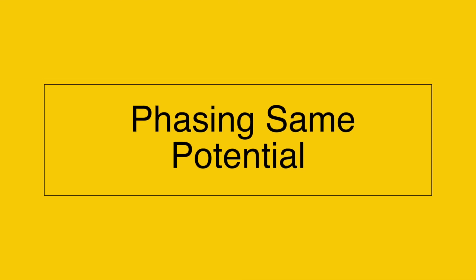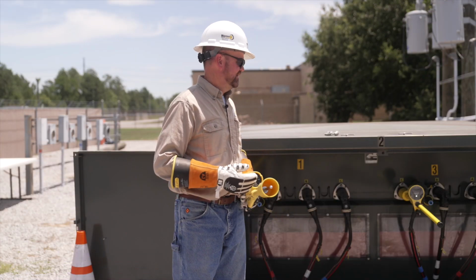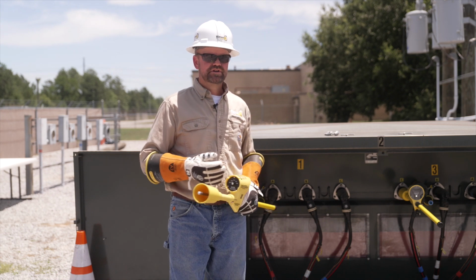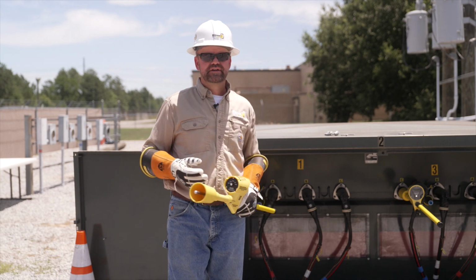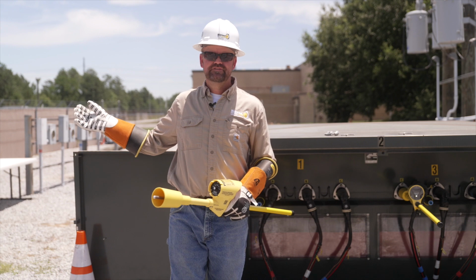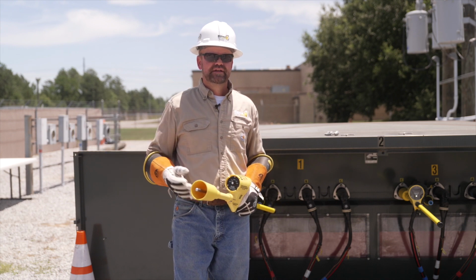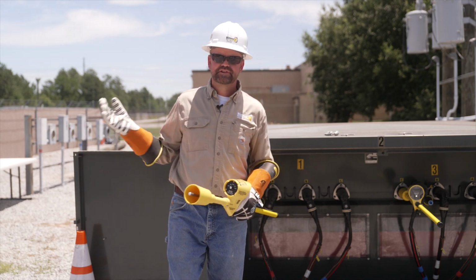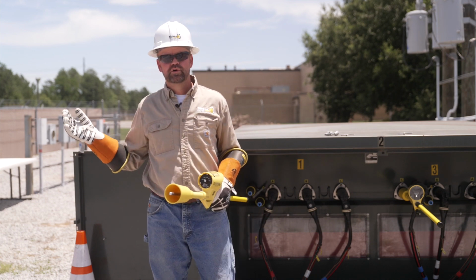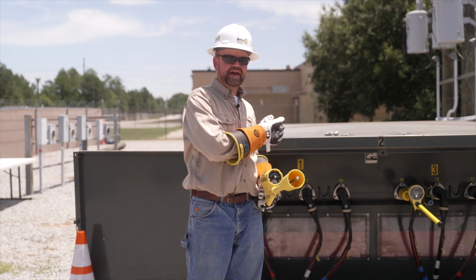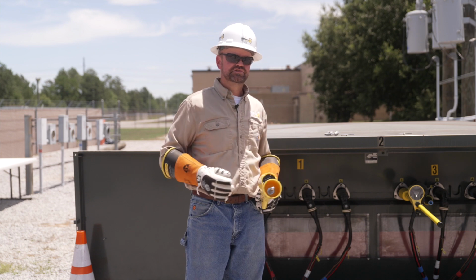So the next demonstration, I'll be phasing URD and same potential. In other words, I have 13.8 kV phase to ground here and 13.8 kV phase to ground over here in this pad mount. And I'm going to phase between this switch and that 3-phase pad mount and determine what phase on the pad mount, the 3-phase pad mount, is feeding this switch.